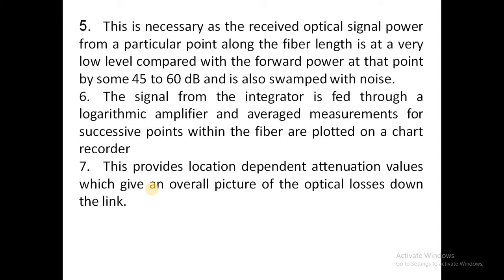So we are not taking the overall average, but we are putting every measurement inside the graph so that you can find out for regular intervals how much loss can happen, which was not possible in the cutback method. In that we were using only an average technique. So if you want to calculate how much loss there is for a particular distance, it was not possible. This provides location dependent attenuation values which give an overall picture of the optical losses down the link.